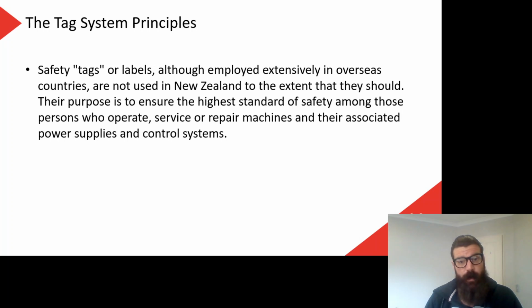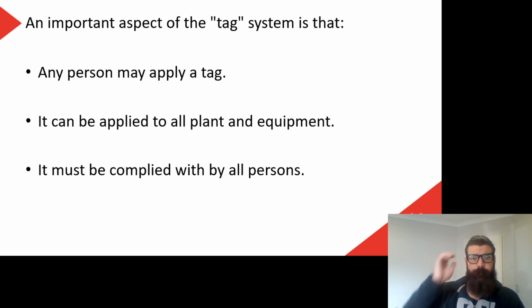They might have lockable valves. Any gas or oil pipeline type system will often have lockable valves. Even water. So if we're doing something where there's a lot of water or high pressure water, you might want to turn off a valve and lock it out, and you'll often find lockable valves on stuff like that. So it's important that if we've got different types of energy, not just electrical energy, fluids or gases under pressure is the common one, that we lock out those types of energy as well.